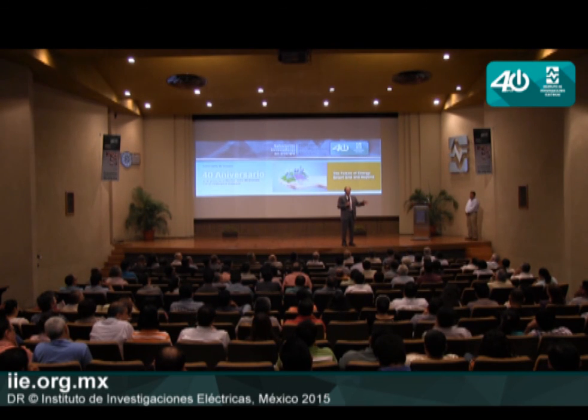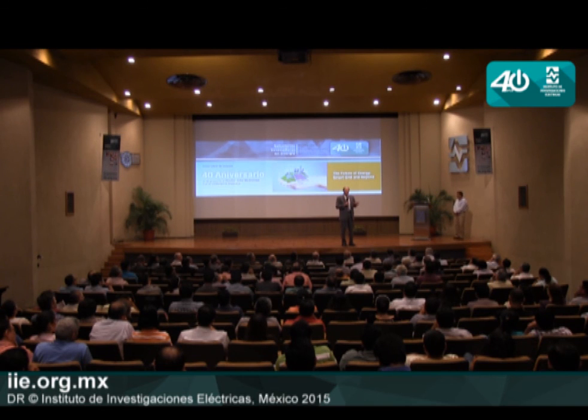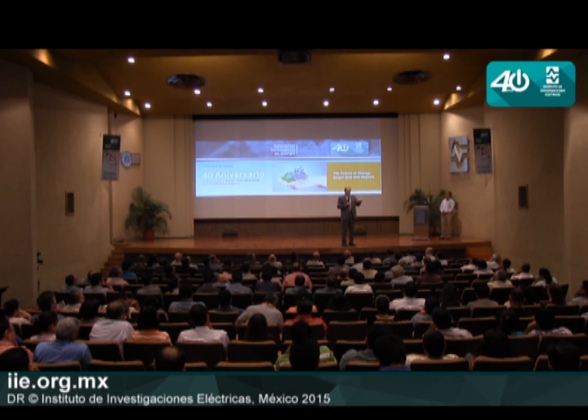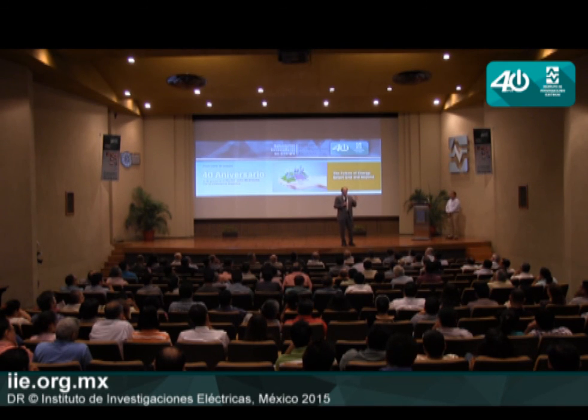I agree with it. Transformers today - typically now when a utility buys a transformer, the standard specification for buying requires a transformer monitoring and diagnostic unit to be bought with the transformer. So when a transformer is being built, those sensors are put inside it at the time of manufacture. But every piece of equipment should have some kind of monitoring.